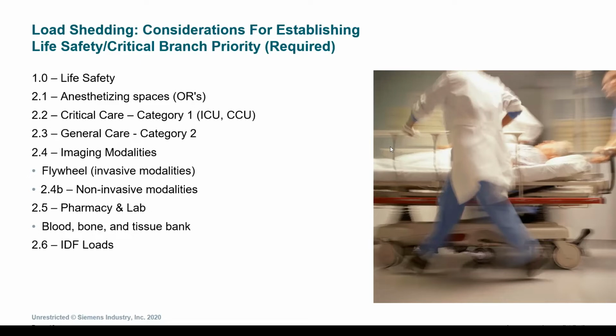From there, we'll go down to the next level of acuity, to critical care as defined by 517, being category 1, including an ICU, a CCU, or a NICU. Additionally, from there, the general care or category 2 spaces, followed by the imaging modalities. It's very common in a healthcare environment that the imaging modalities are broken up into 2 transfer switches. First being the invasive imaging modalities, such as an angio, EP, or CT, then followed by the non-invasive modalities, such as an X-ray, a fluoro. And based off the acuity, we want to make sure that the invasive transfer switch is higher priority.